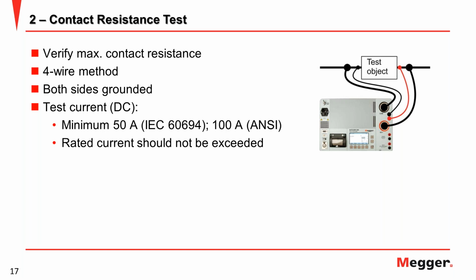And also corrosion. To make sure there is no corrosion on the main contact, you need to do this contact resistance test, because this test can detect corrosion between the contacts inside the breaker. There are two standards for testing circuit breakers for contact resistance. IEC 62271-100 states minimum 50 A, and other standards like ANSI state minimum 100 A. Actually for testing contact resistance, we can do it with 1 A, maybe 10 A. In principle, it is the same. You can test with lower current, but for the circuit breaker, if you follow the standard, you should use high current. But please remember, not more than the rated current of the circuit breaker.